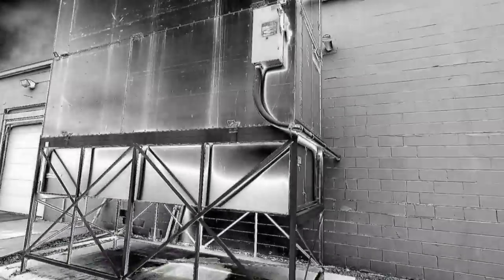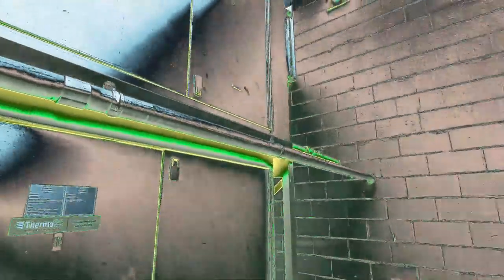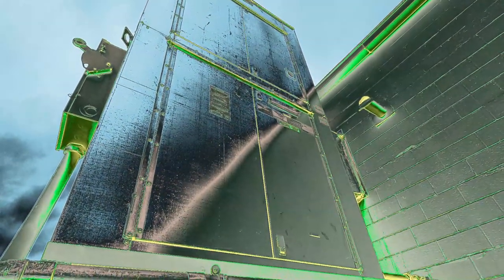Alright, got a makeup air unit here, a Thermal Tech. What we got going on is it's not regulating temperature very well and we need to find out what's going on. What I noticed was when I kicked it on, it squeals like a pig. So it sounds to me like the belts are loose.